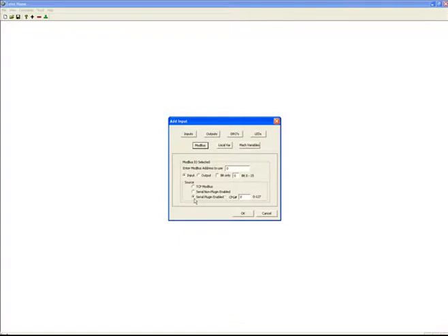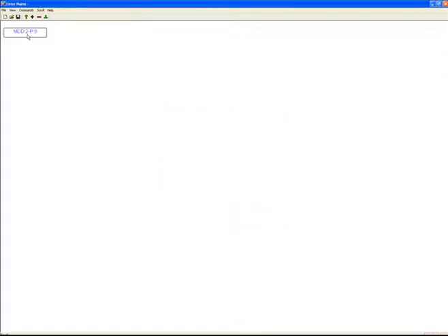And you can see that when you select serial plug-in enabled, not only do we set a Modbus address up here, and that number would be 0 to 127 for the data within that configuration group, but you set a configuration number. So by telling it that I want, say, address 2 from serial plug-in enabled configuration 0, we would get Modbus address 2 plug-in enabled, and it is currently in configuration 0, and that's what this Mod 2 P0 means. Modbus address 2 plug-in enabled configuration 0.